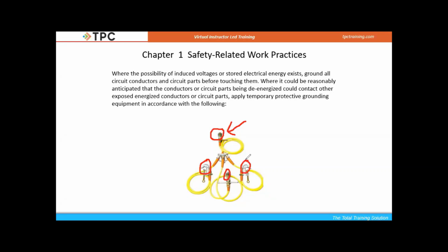I have taken a look to see how many sources of supply I've got. I have interrupted the load current. I have opened the disconnecting device. I've done my visual verification, released stored electrical energy and mechanical energy, put my lock on it, did live, dead, live, and now I'm putting these on to make sure that if it does become re-energized, we are going to allow that overcurrent device to operate.